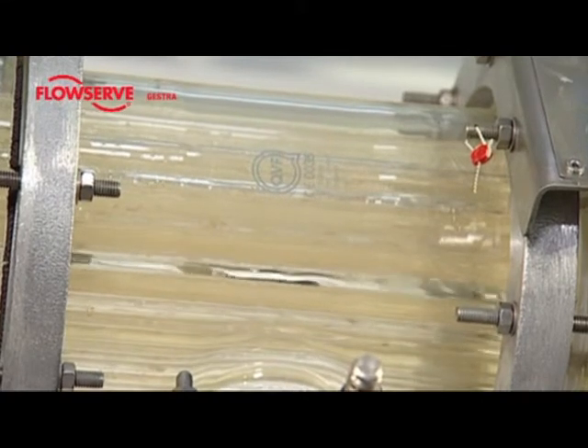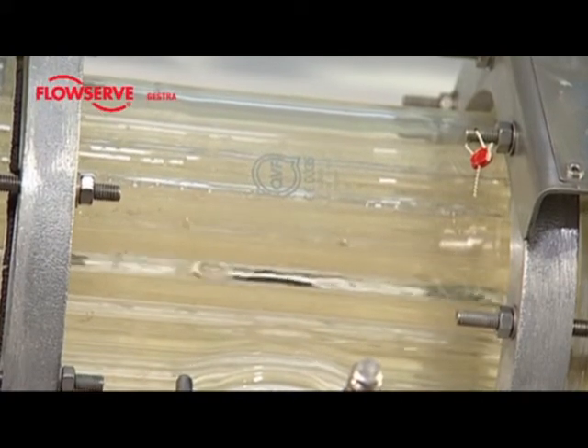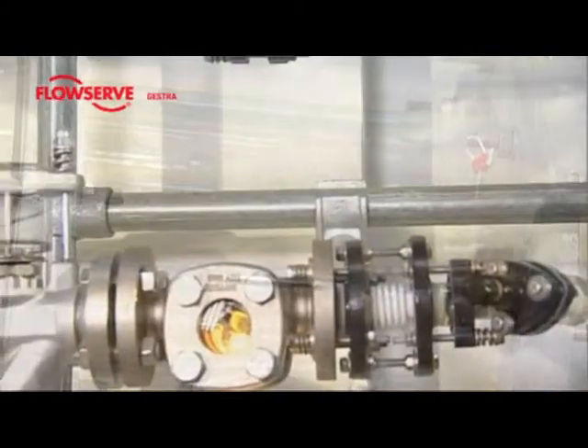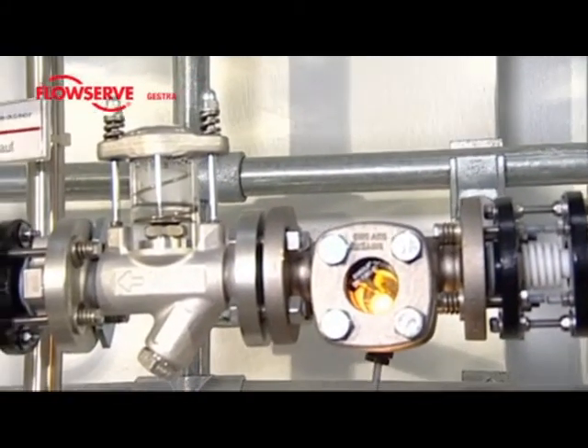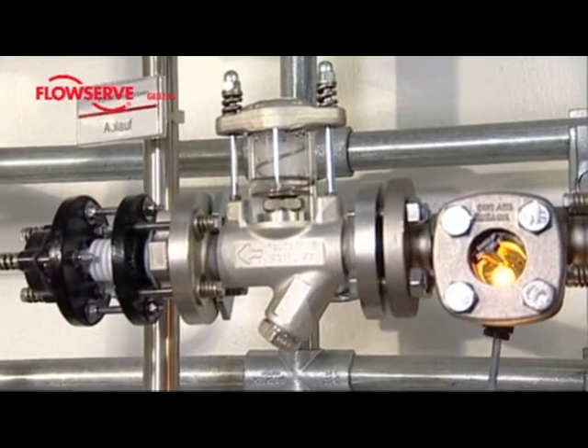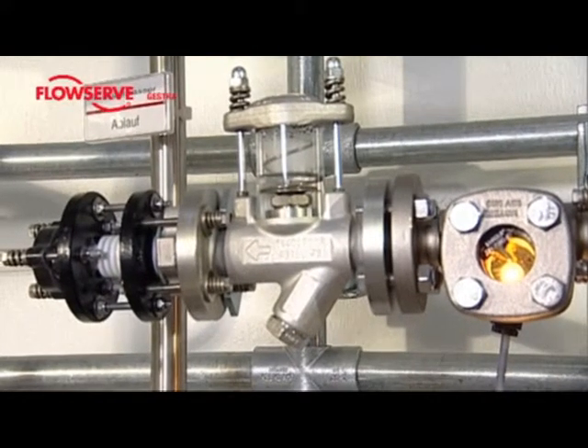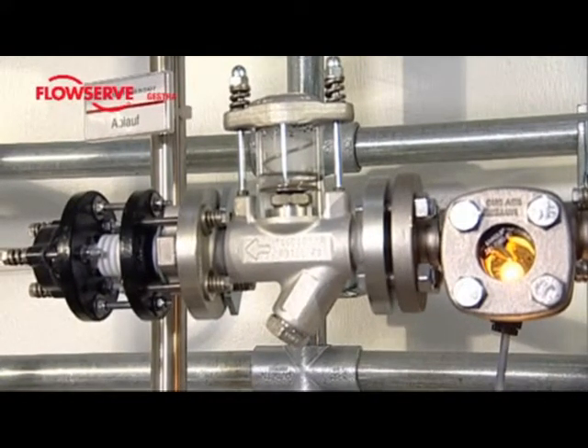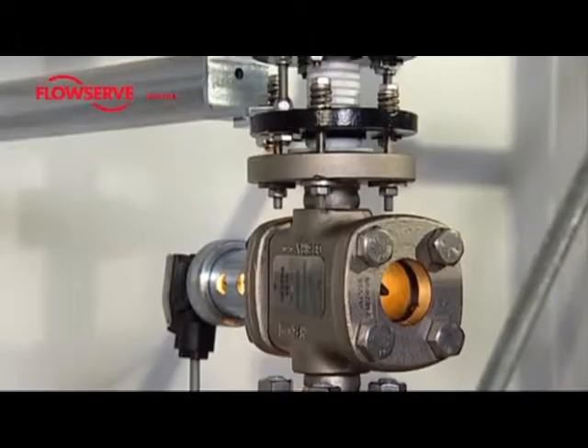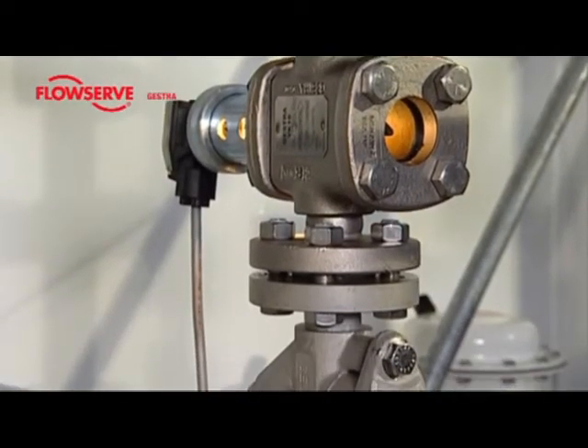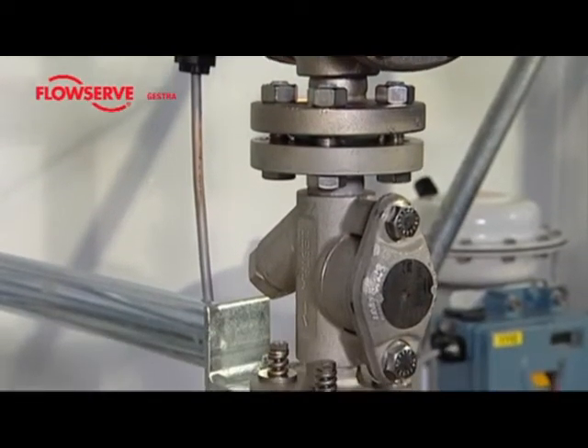It's recommended that thermostatic steam traps not be used in the case of large heat exchangers controlled on the steam side. For such applications, float traps are recommended. However, for the drainage of steam lines, kettles, air heaters, uncontrolled heat exchangers and so on, membrane steam traps can be used without any problems.